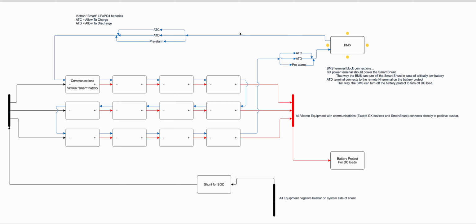So if the BMS sees that it has continuity from ATC here on the output to the ATC here on the input, then it knows that every single battery is passing continuity through. So then it knows, hey, the batteries are all telling me that it's okay to charge. Same with the ATD. If all the batteries are passing continuity through the ATD, then the BMS knows, okay, it's okay to discharge. And same with pre-alarm.